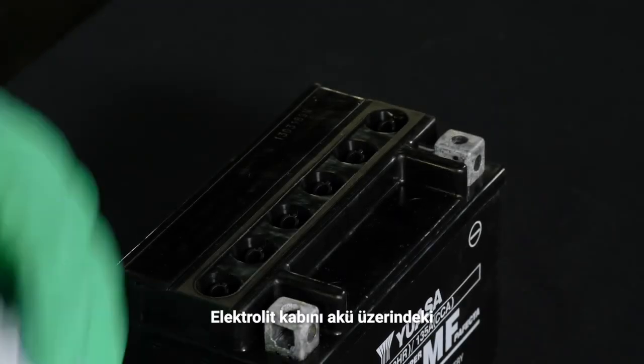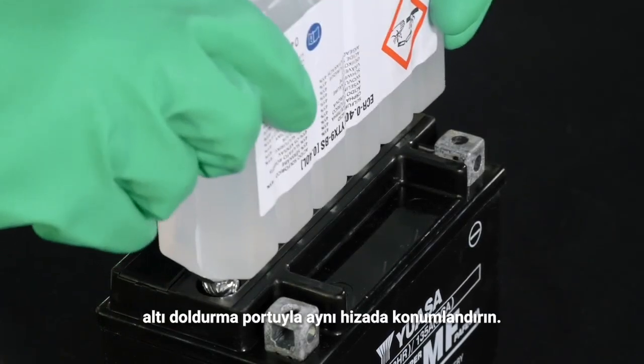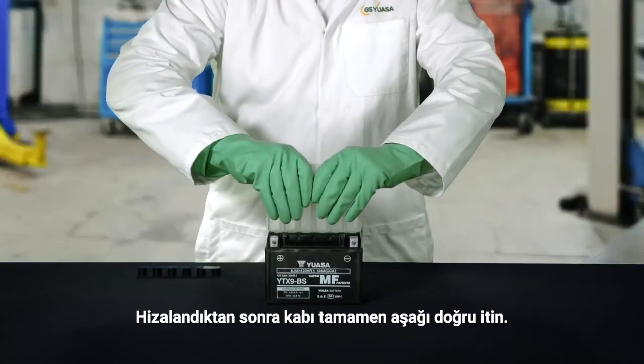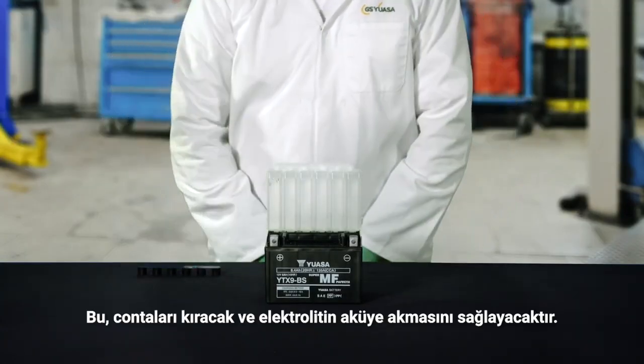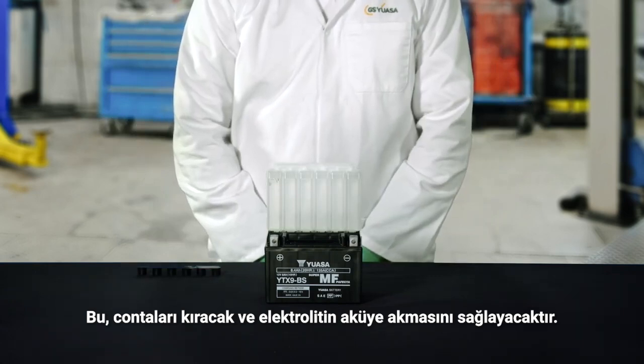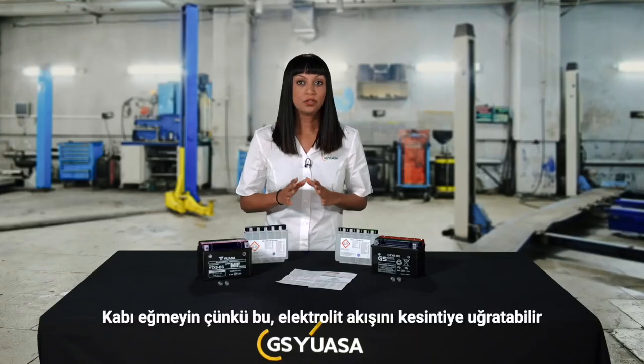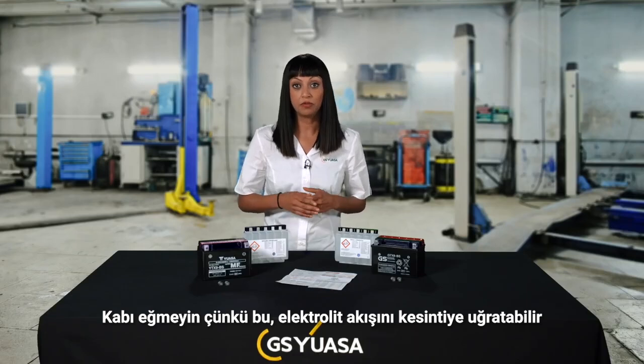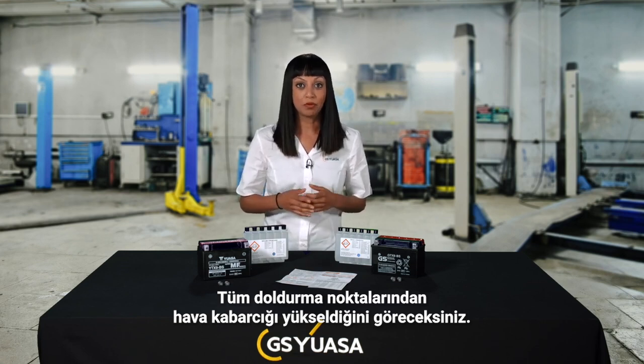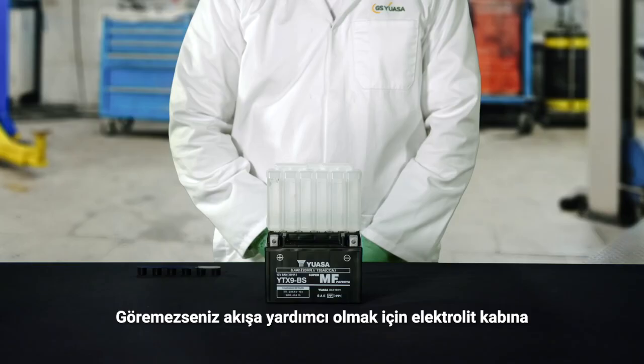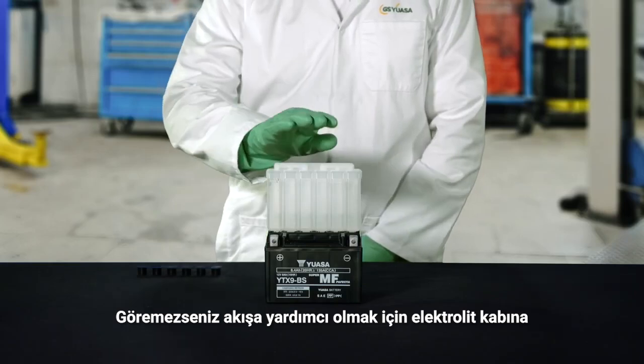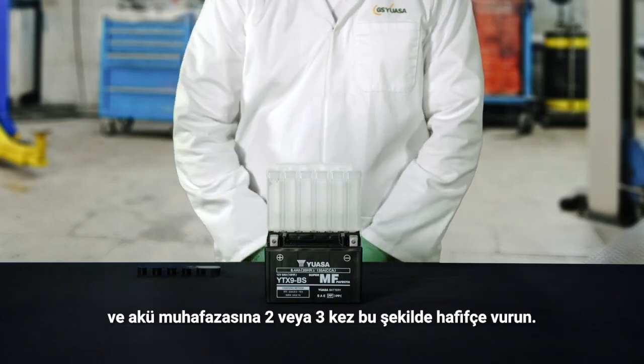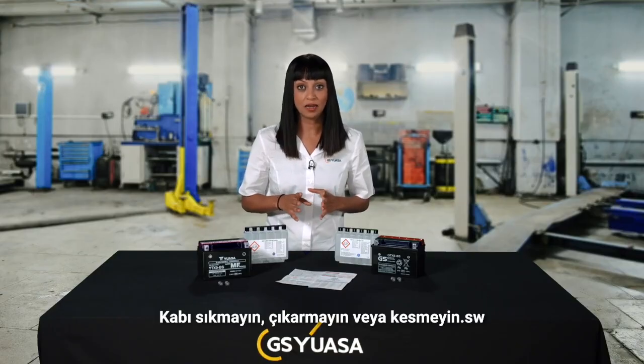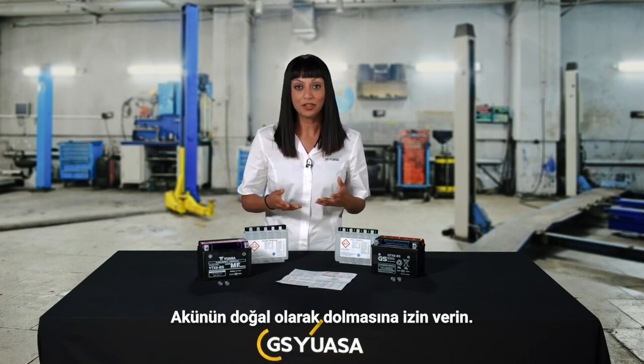Now position the electrolyte container in line with the 6 filler ports on the battery. Once aligned, push the container fully down. This will break the seals and the electrolyte will begin to flow into the battery. Do not tilt the container, as this may interrupt the flow of electrolyte or cause leakage. You should now be able to see air bubbles rising from all the filler ports. If not, gently tap the electrolyte container and battery casing 2 or 3 times to assist the flow, like so. Do not squeeze, remove or cut the container. Allow the battery to fill up naturally.